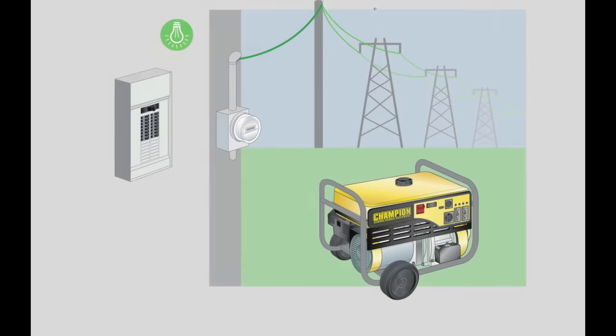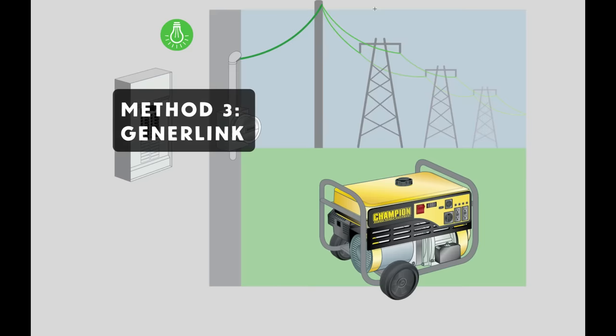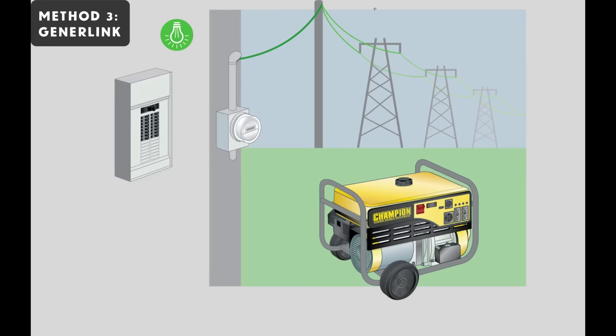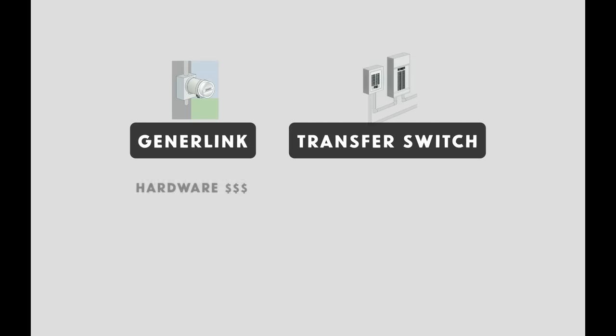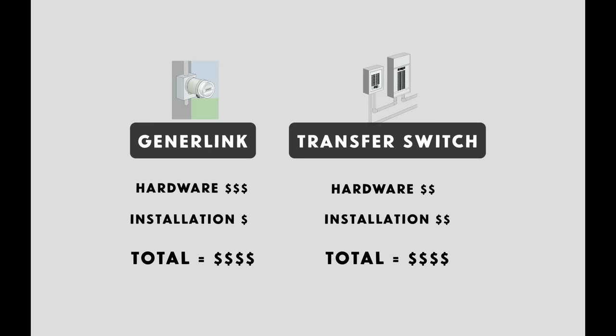The third legal method for connecting your generator to your house uses a piece of hardware called a GenerLink. As far as I know, it's the only thing of its kind out there. And it actually requires the least modification to your home electrical system. It's not a perfect system, though. There are some drawbacks, as I'll explain. But essentially, the GenerLink unit is a cylinder that fits between your meter and your meter base. The cost of this unit is going to be more than the cost of a transfer switch and panel that I discussed previously. But the installation costs are very low. It doesn't take an electrician very long to install one of these. So, on balance, I think the GenerLink is probably going to be about the same amount of money as the transfer switch option.